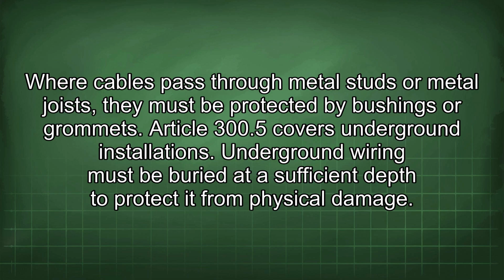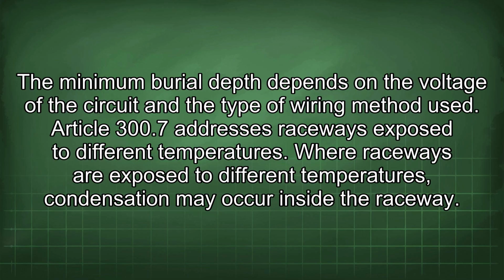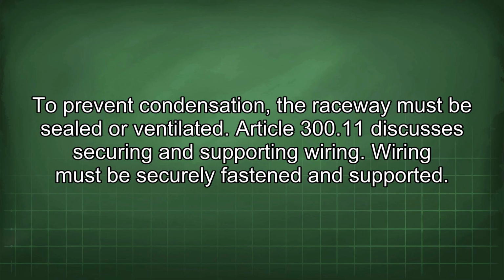Article 300.5 covers underground installations. Underground wiring must be buried at a sufficient depth to protect it from physical damage. The minimum burial depth depends on the voltage of the circuit and the type of wiring method used. Article 300.7 addresses raceways exposed to different temperatures. Where raceways are exposed to different temperatures, condensation may occur inside the raceway. To prevent condensation, the raceway must be sealed or ventilated.